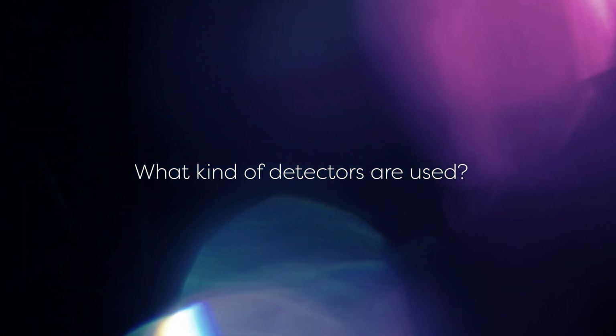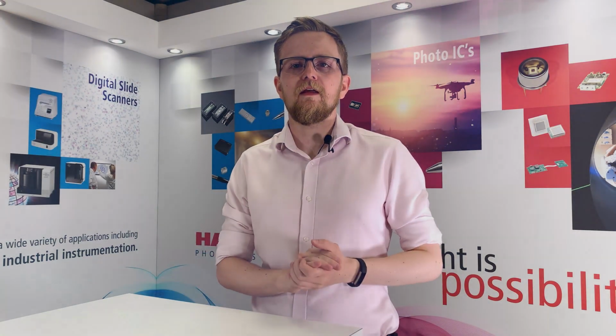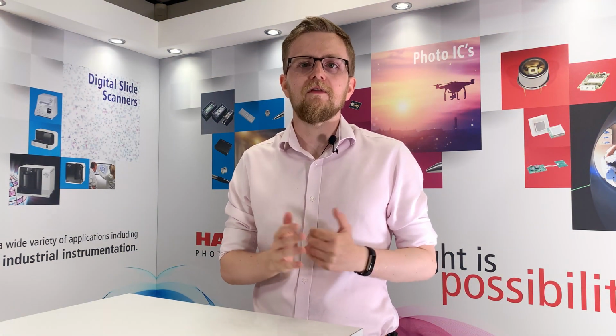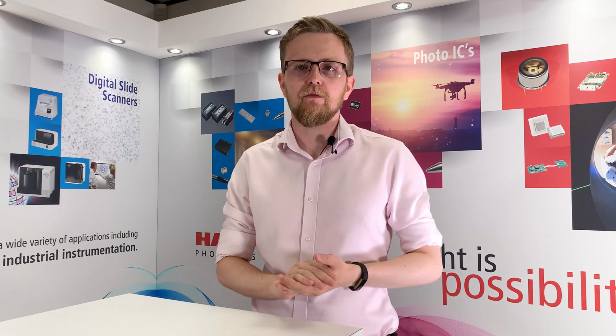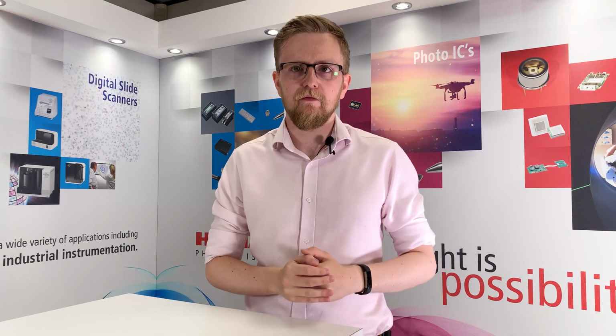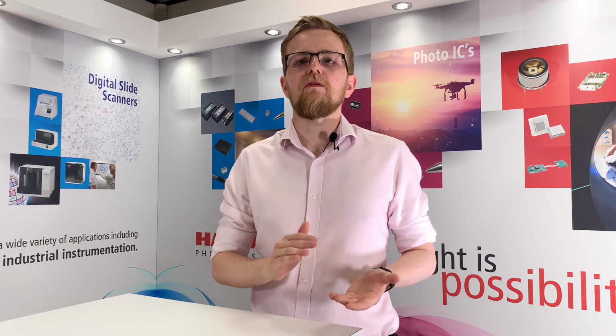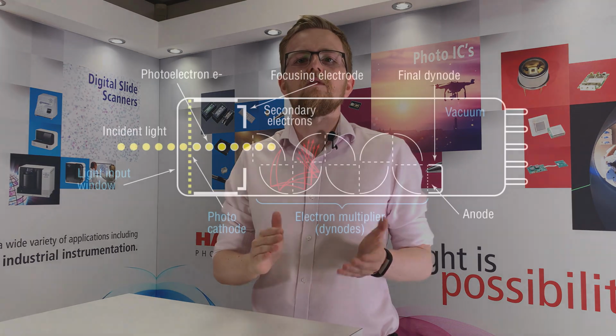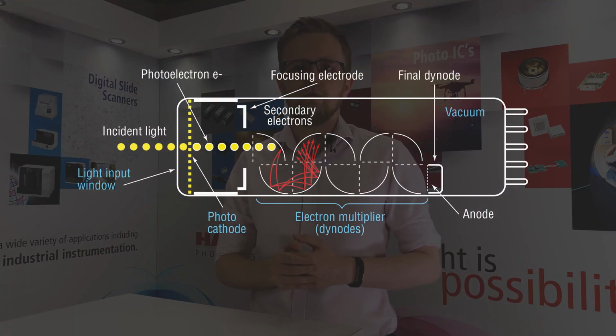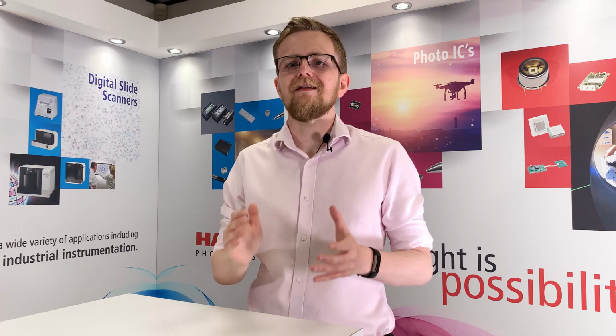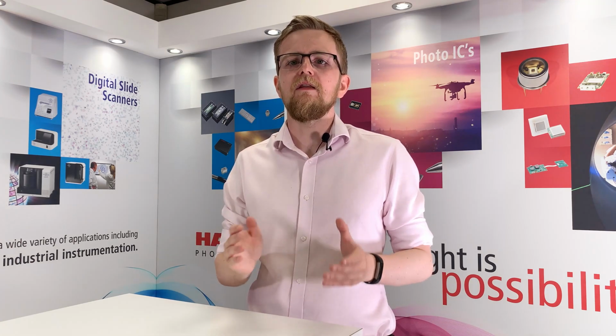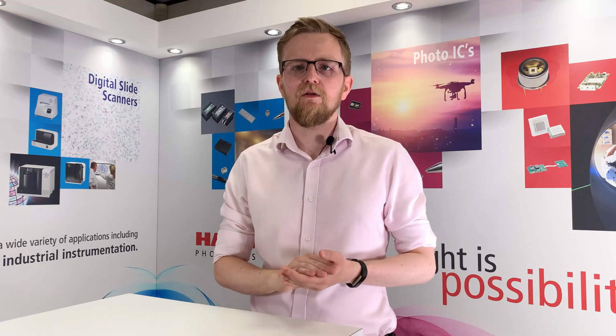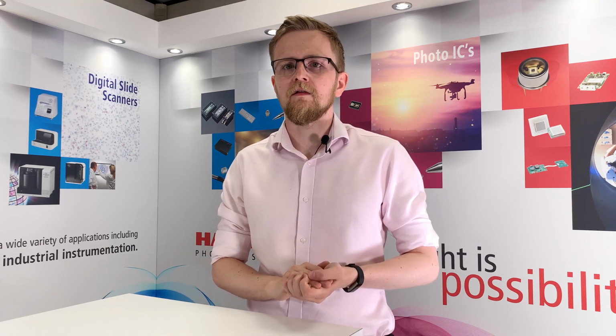What kind of detectors are used? Scintillation detection has been around since 1903, but as it only produced faint light visible via microscope, it was imprecise and impractical outside of lab spaces. However, with the development of the photomultiplier tube, or PMT, which uses a series of dynode stages to increase the number of electrons through the device, this allowed even small instances of incident light from the scintillator to be detected by multiplying the current created by as much as 100 million times. The combination of this high gain coupled with low response time made these devices perfect candidates for a variety of applications and gave birth to the modern scintillation detector.